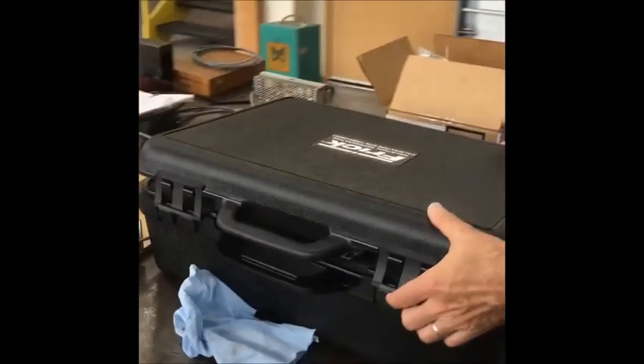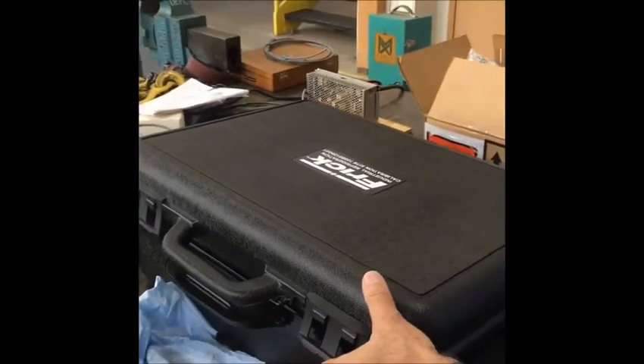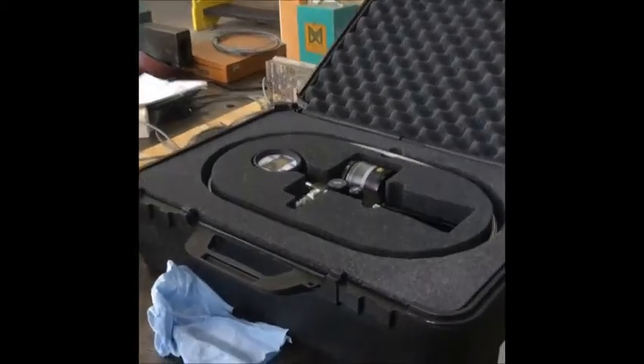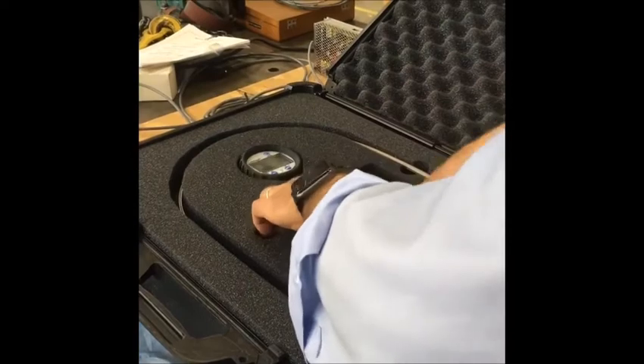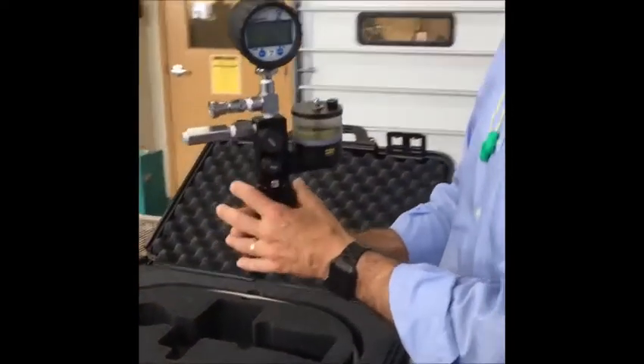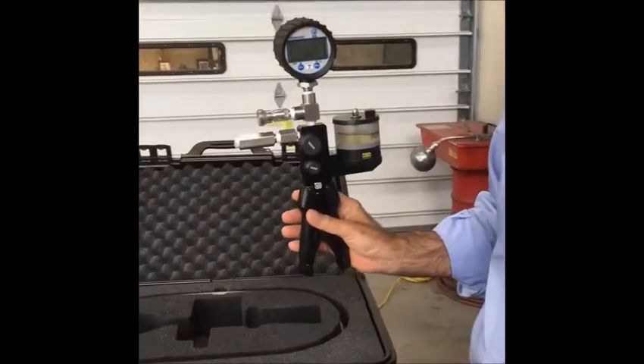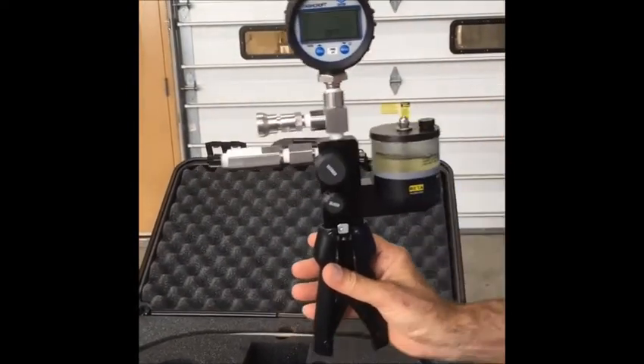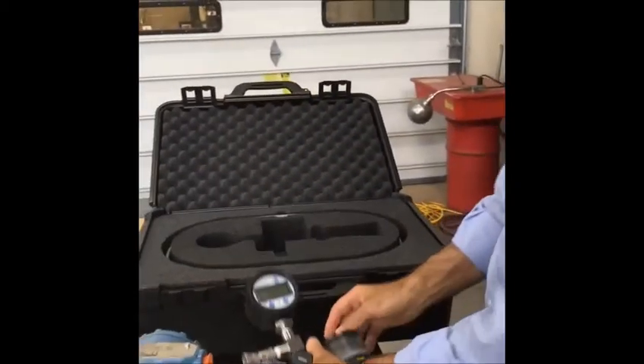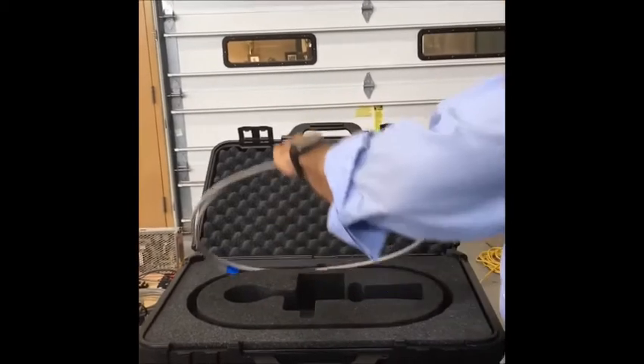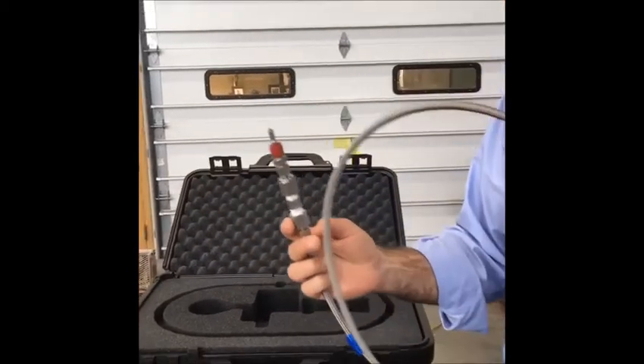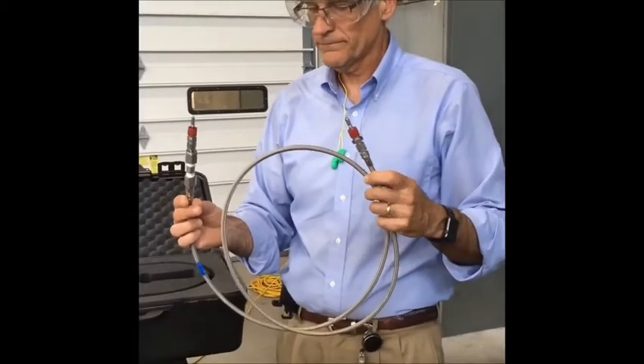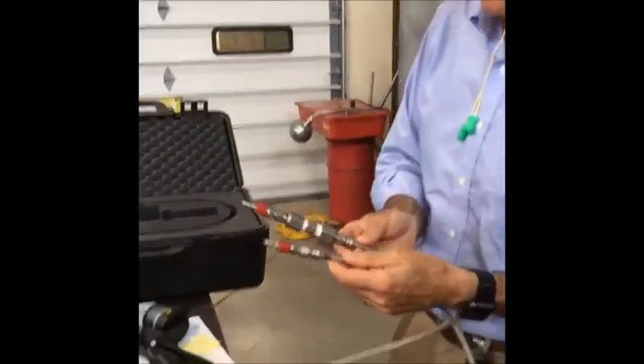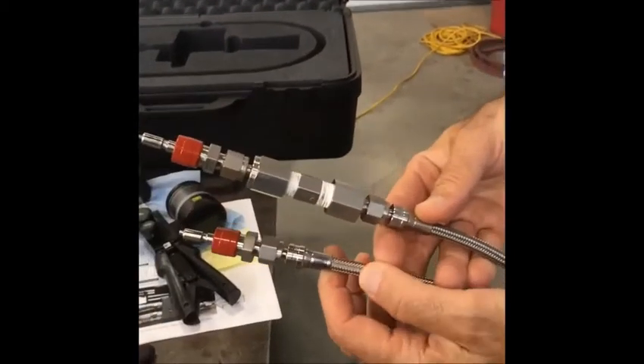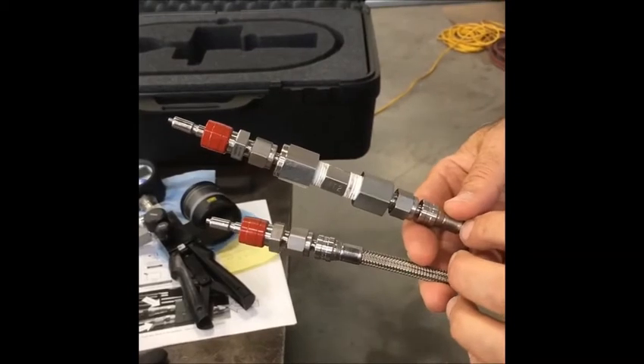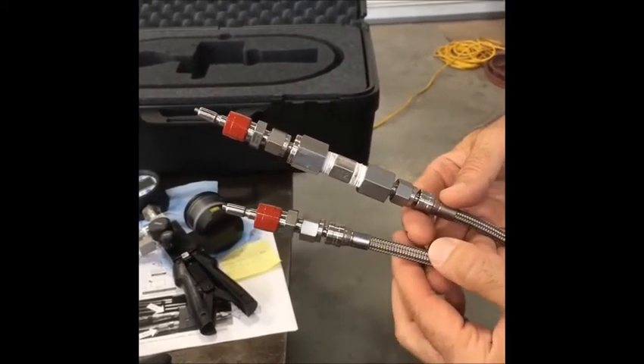Okay, so here's our plastic carrying case that goes with the test pump. And here we've got our calibration pump, so we'll just take this out of here. And you get a shot of it there if you want. See what that looks like. And wipe just a drop of oil off of it. And also in the test kit is our calibration hose. These are special hoses that come with the pump. They're quick connect hoses. And one thing you'll notice as you look at the hoses, the two ends are different. The longer end is the one that goes into the test block. The shorter end is the one that goes into the calibration pump.